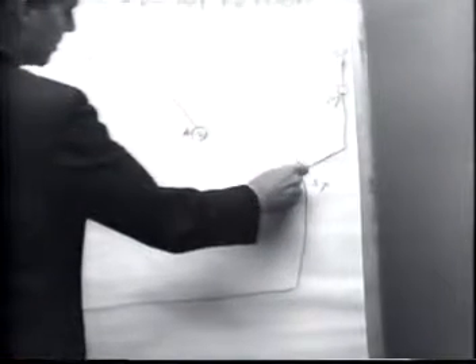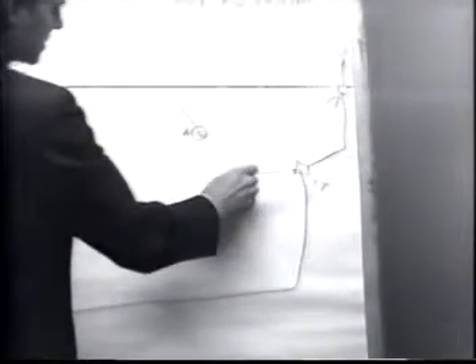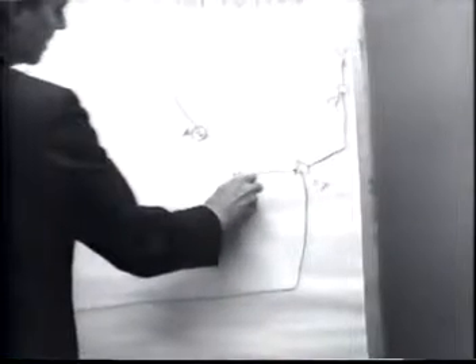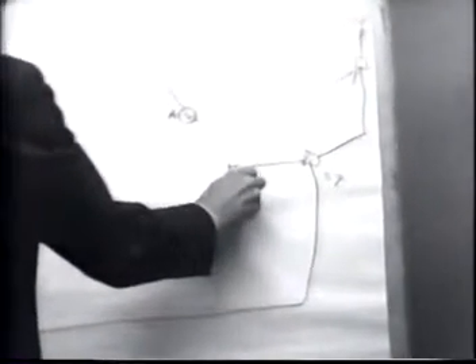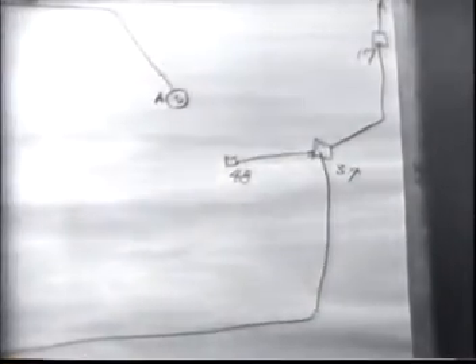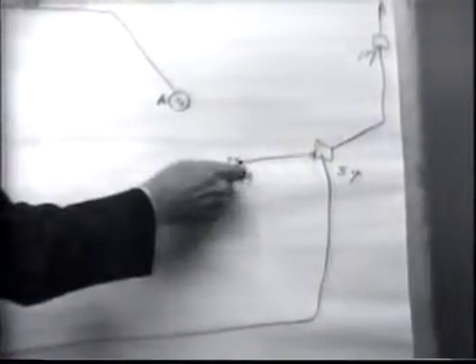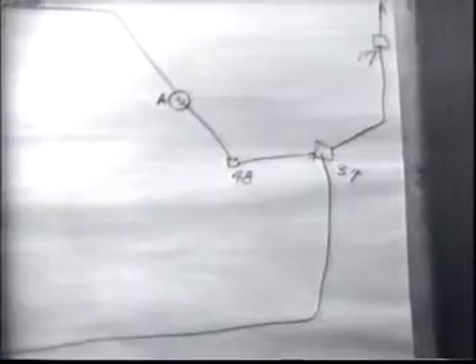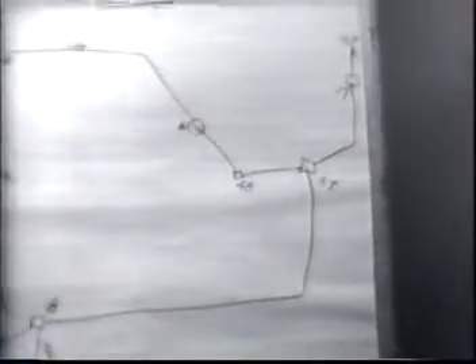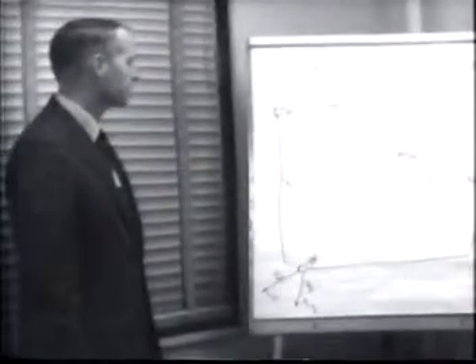At the same time, from substation 39, a line was built towards Silvis, where at substation 48 we have a transmission substation and also some distribution to serve the new John Deere foundry there. And then finally a line was completed from substation 48 to Riverside, thus completing a 161 kV loop around the Quad Cities. And at our major substations here, we can make interconnections to other utilities and allow room for expanding into the next stage of development, which we'll talk about in a minute.